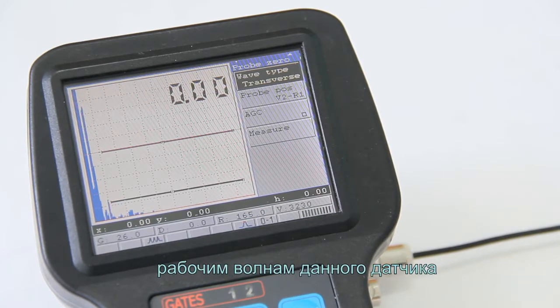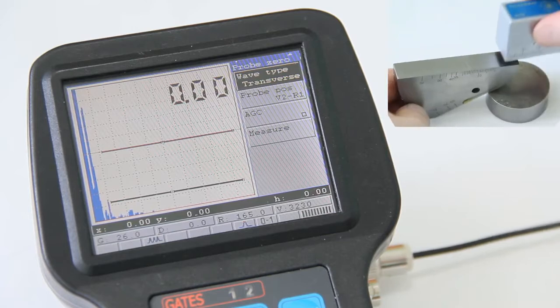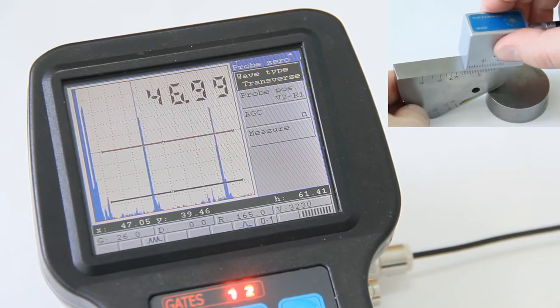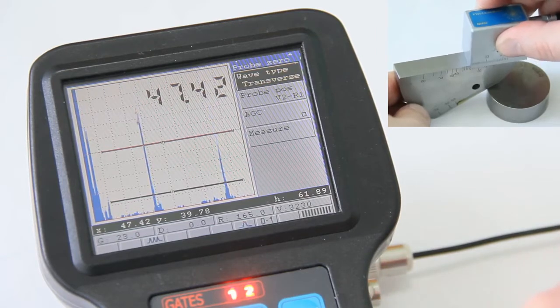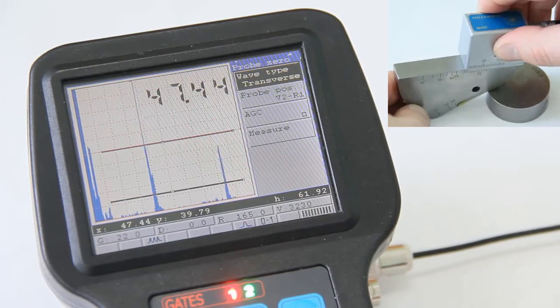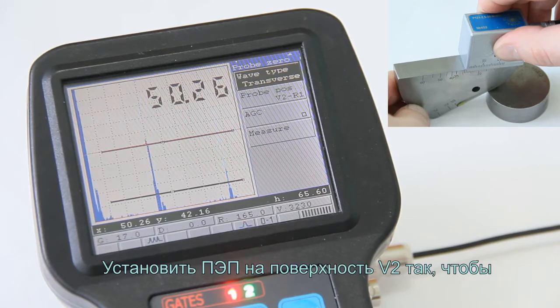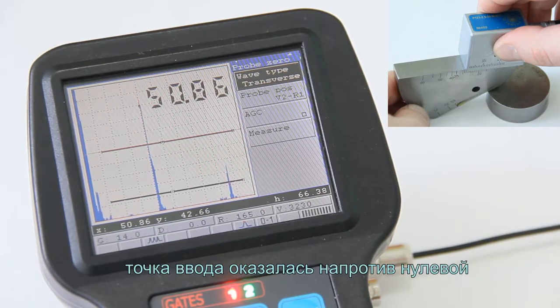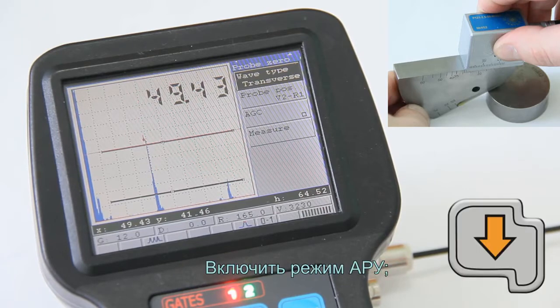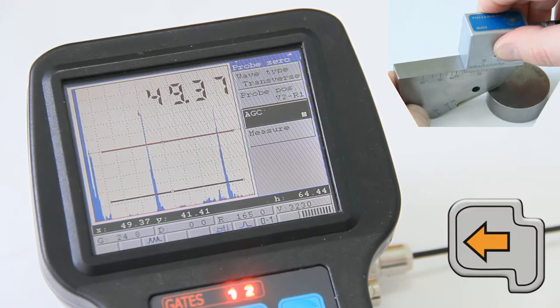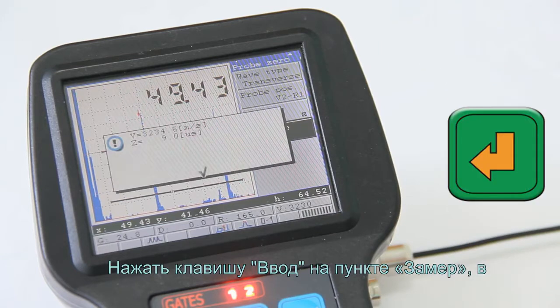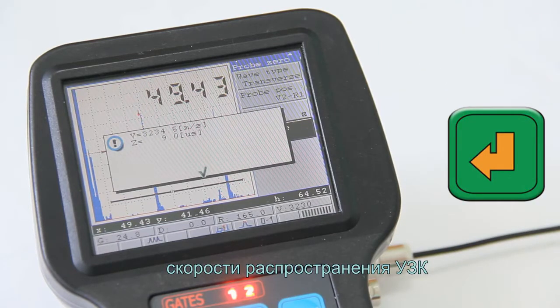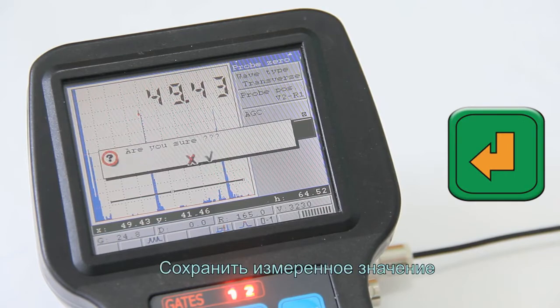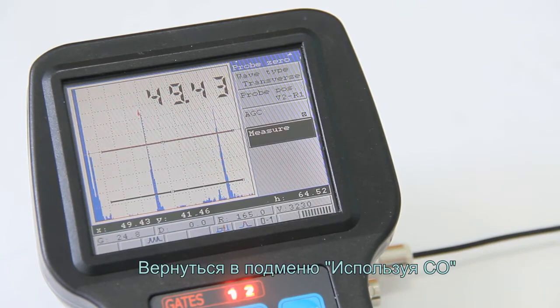Select the wave type that corresponds to the operating waves of a selected probe. Place the probe on the working surface of V2 block in such a way that the index point to be in front of the 0 mark of V2 scale. Switch on the AGC mode. Press Enter key in Measure menu item to activate the measurement of sound velocity and probe 0. Save the measured probe 0 value.